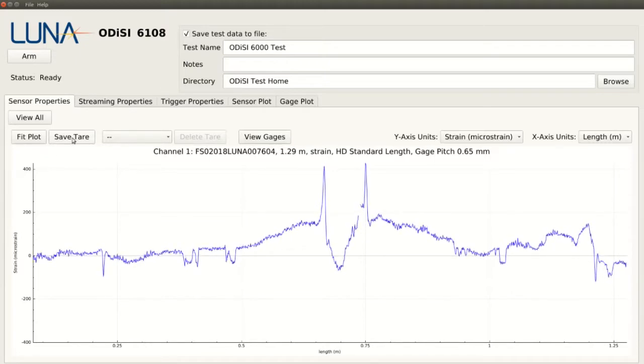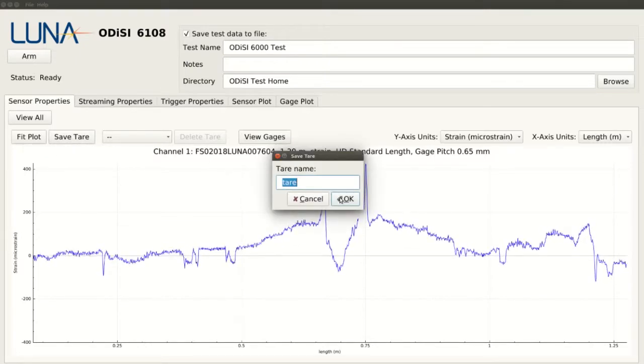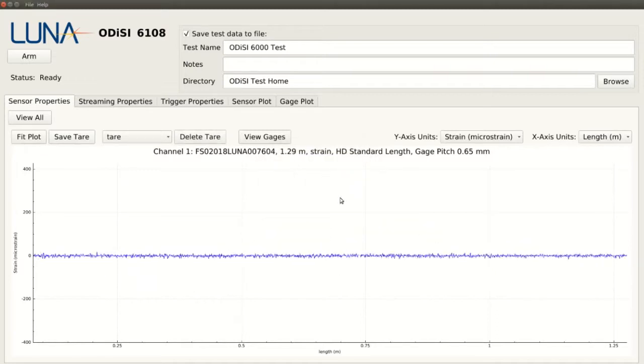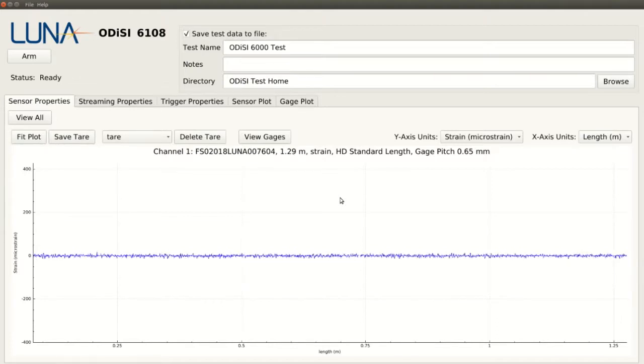If we want to zero our measurements, we can save a tare, and now any changes from this state will be reflected in the data. This tare is saved in the data file and can be very useful in evaluating the residual strains after an instrumented component is processed or tested.